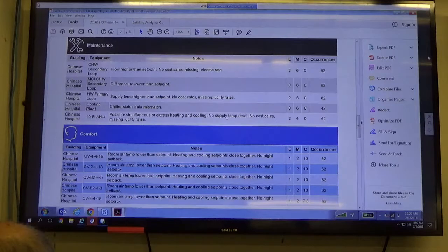And then no supply temp reset. It's saying that the supply temperature set point was constant. Consider calculating or resetting the supply temp based on terminal load or outdoor air temp or however you want to do it, but that's an energy saving opportunity by implementing a supply temp reset schedule. And not only does it do it for supply air temp on air handlers, it'll flag if the chill water supply temp stays constant. It'll recommend to reset that up as the outside air temperature goes down, and vice versa with the hot water supply temp. But as we get into doing more of these monthly meetings and reports, we'll get into some of that and discuss that.